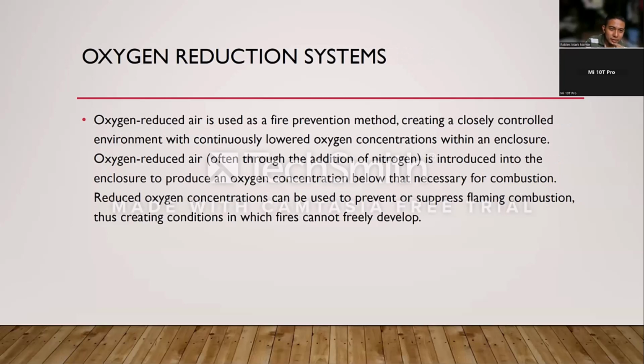Oxygen reduction systems are used as a fire prevention method, creating a closely controlled environment with continuously lowered oxygen. It is introduced into the enclosure to produce an oxygen concentration below combustion. Its concentration can be used to prevent or suppress flaming combustion, creating conditions in which fires cannot freely develop.